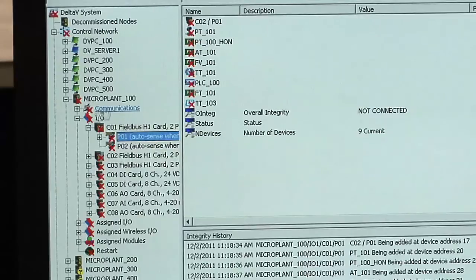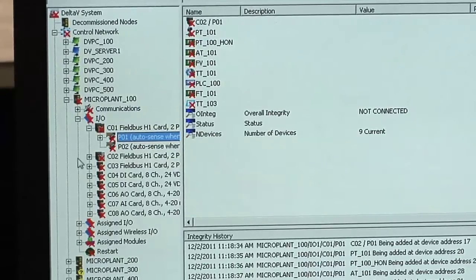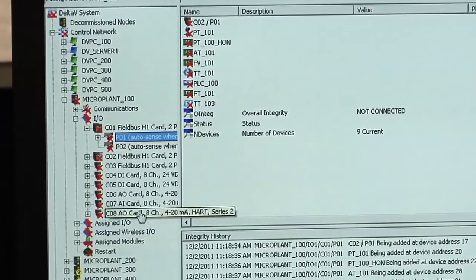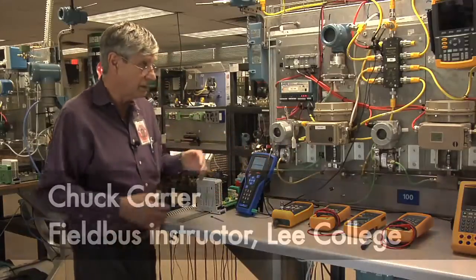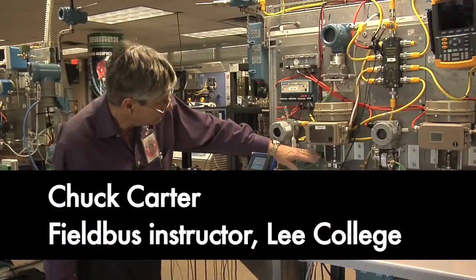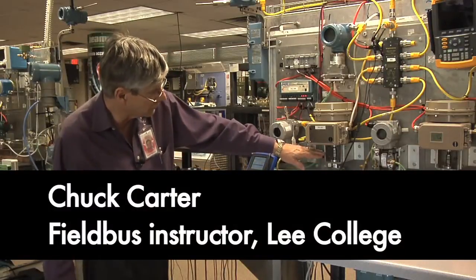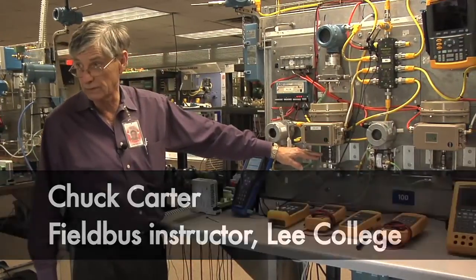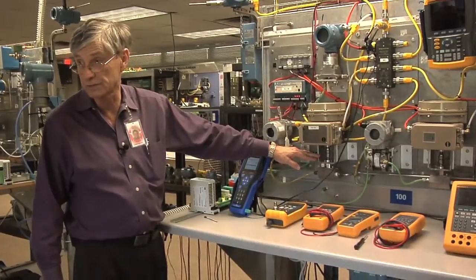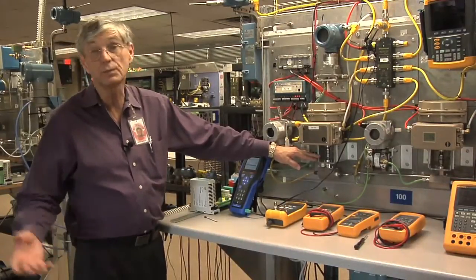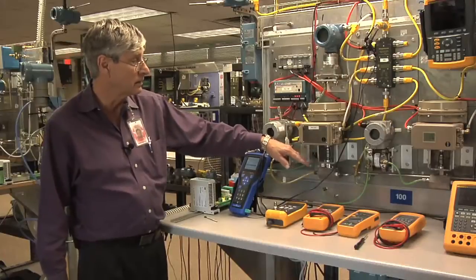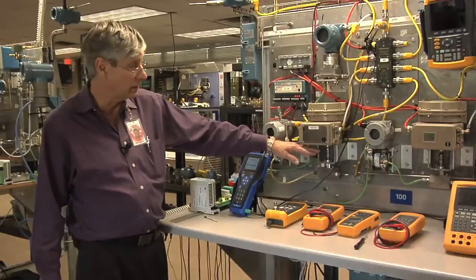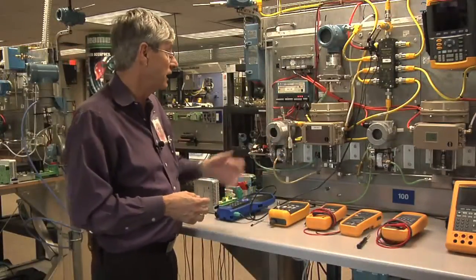However, when we return and look at the valve, we'll notice that the valve position is holding at about the 40-50% that it was at. So with the host's power removed, the valve is holding that position. We didn't hear or see the valve go to any kind of failure position because we have it set up with the control in the field that on failure it's going to retain its last set point and keep working.